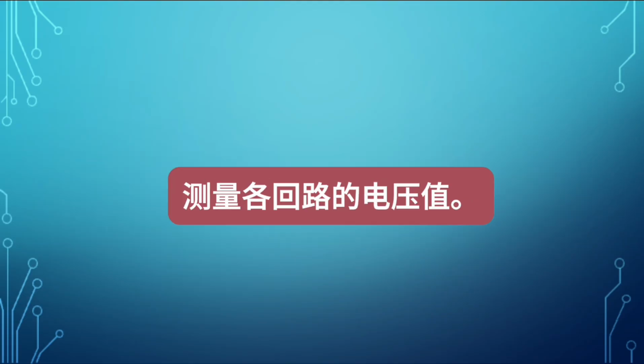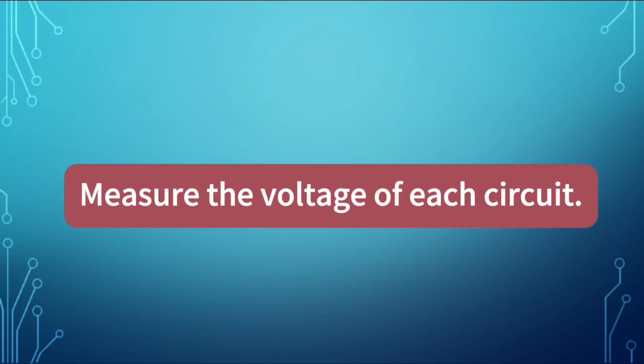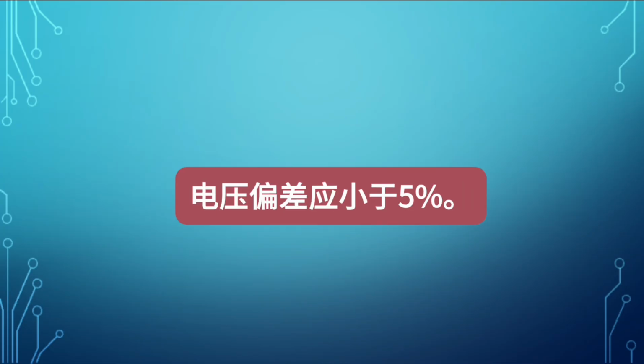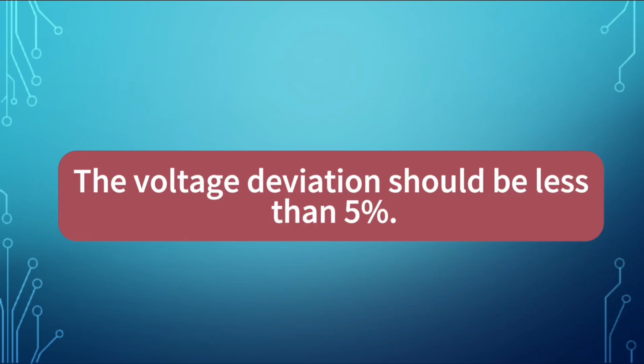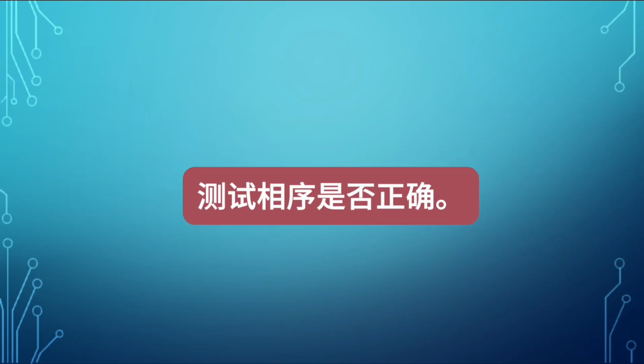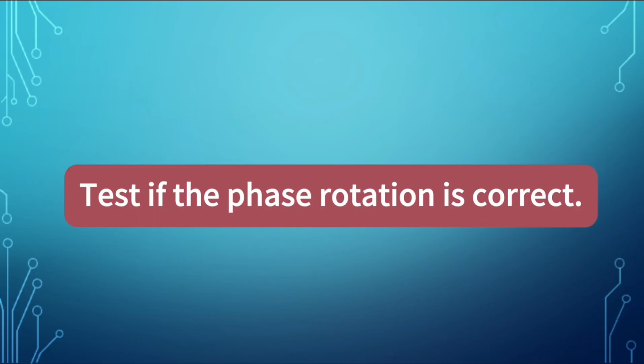Measure the voltage of each circuit. The voltage deviation should be less than 5%. Test if the phase rotation is correct.